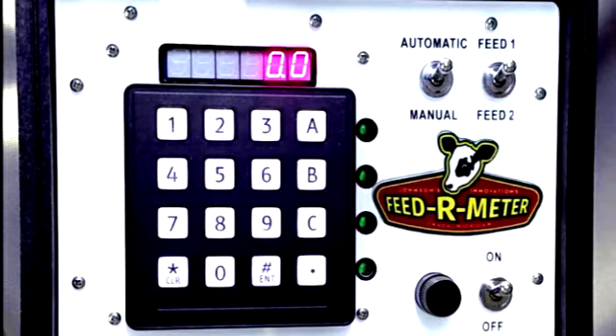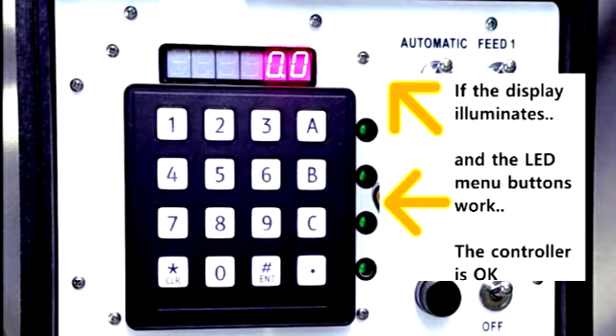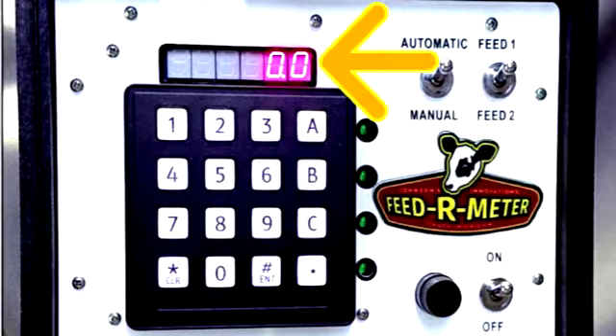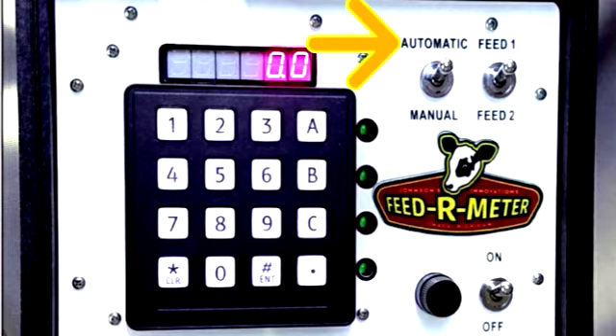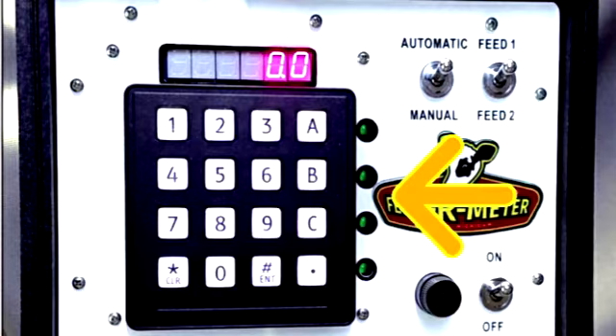Only disassemble parts as a final option. If your system isn't operating correctly, turn on the controller. If the display illuminates and you can interact with the buttons in the menu, the controller is okay. Make sure that when you turn it on it says 0.0, you're in automatic, and that all of the lights are out next to the menus.